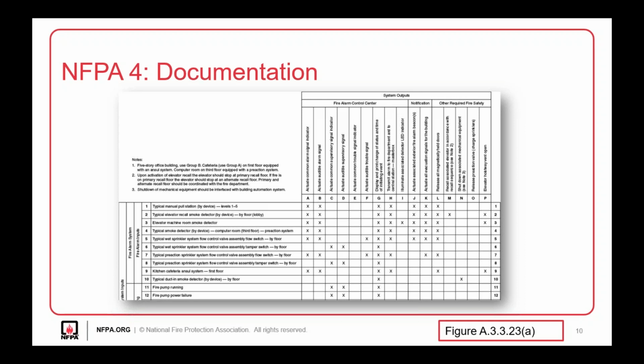So some of you might already be familiar with the input-output matrix, and that's what's shown on the screen right now. Basically, the input-output matrix shows how the building will operate. As you see on the screen, it shows the output on the top columns for every given input into the system. And the input-output matrix is something that's created by the system designer, and it's used by the integrated testing agent when they're creating their test plan. So essentially, this test plan is created to ensure that the building is operated as shown in this input-output matrix.